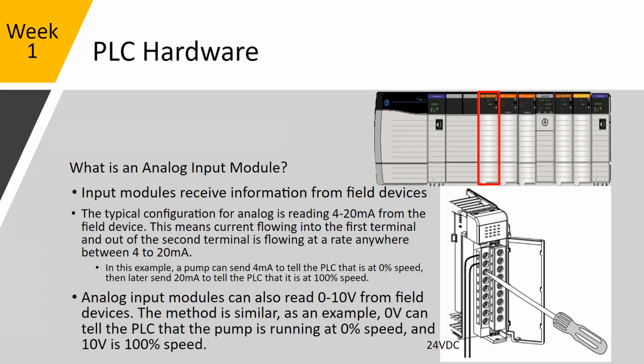The problem with using a 0 to 10 volt signal is that if you were to lose one of your wires, say it gets cut in a door or a terminal block shakes loose, 0 volts is a valid signal, so your PLC wouldn't necessarily fault check that. Seeing 0 volts would mean that the pump is running at 0, whereas if you have a 4 to 20 milliamp loop and the wires disconnect and you start receiving 0 milliamps, then the PLC would be able to recognize that there's a fault condition there.